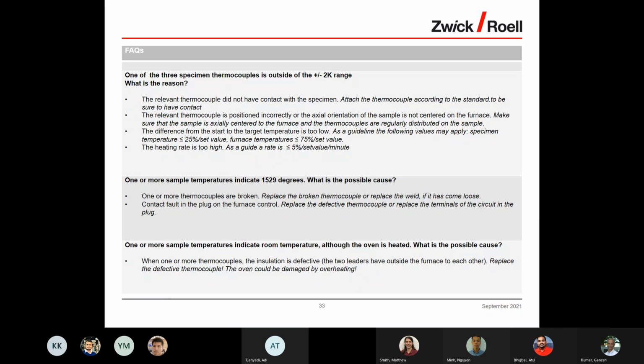One or more sample temperatures indicate 1529 degrees. What is the possible cause? One or more thermocouples are broken. Replace the broken thermocouples or replace the weld if it has come loose. Contact fault in the plug on the furnace control. Replace the defective thermocouple or replace the terminal of the circuit in the plug.